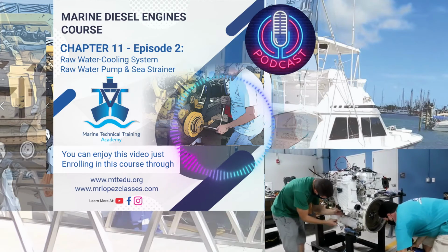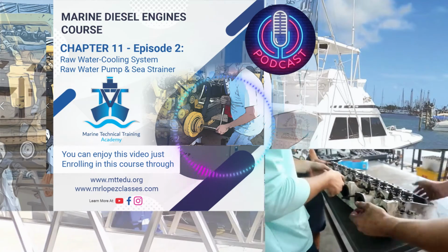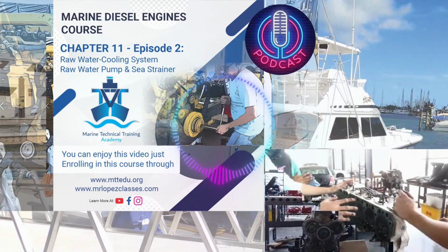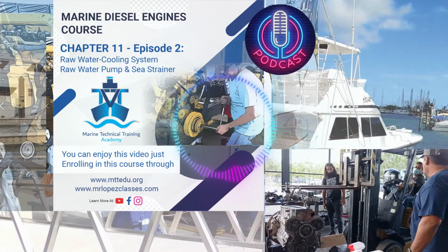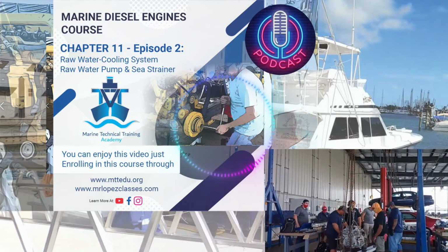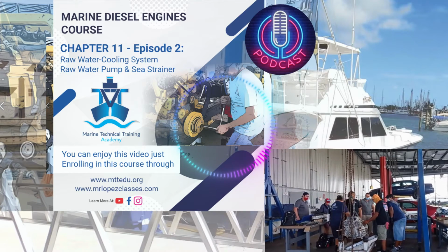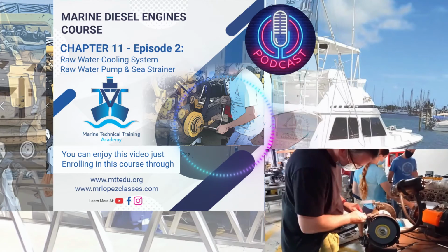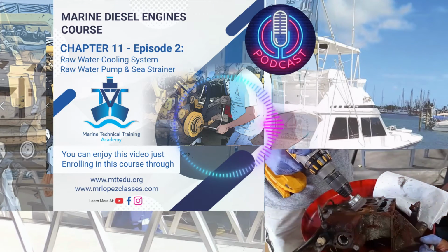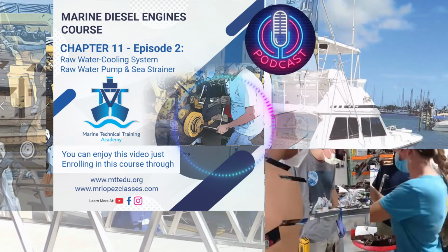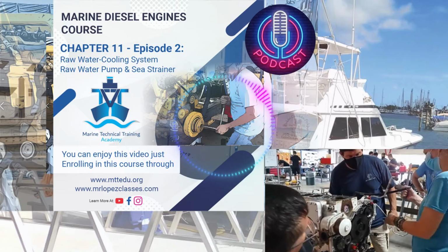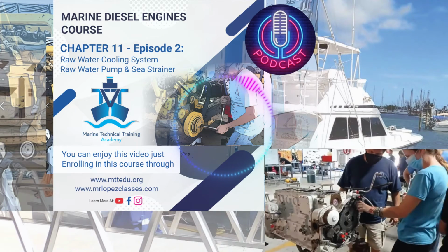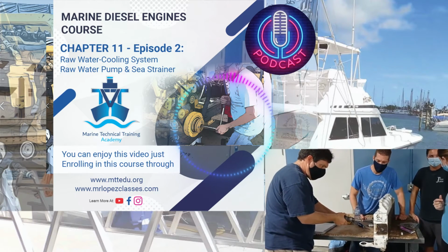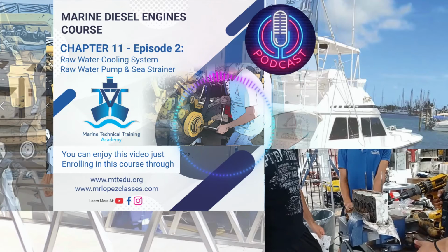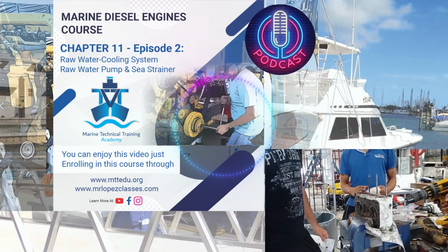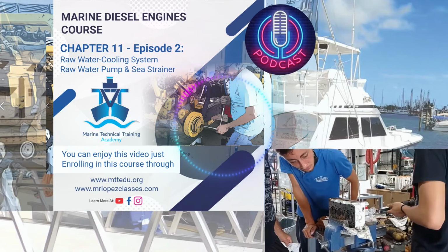What is the other important thing before you install the impeller? Verify that the diameter of the key here is equal to the diameter of the groove in this particular pump. There are other pumps that don't use the spline and the groove. They use another type of engagement procedure. But in this particular case, you need to verify that this diameter is equal to this in order to introduce the impeller properly. There are different types of couplings, and you need to verify that the coupling is clean, and always use marine grease to install the impeller. The marine grease is a lithium grease. Don't use automotive grease, use marine grease.